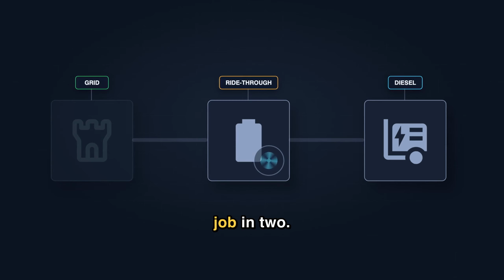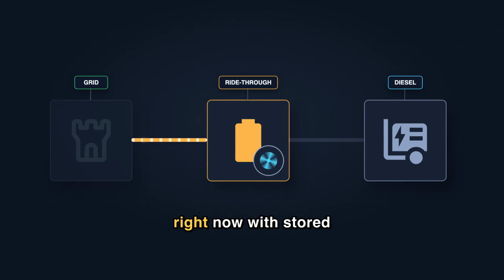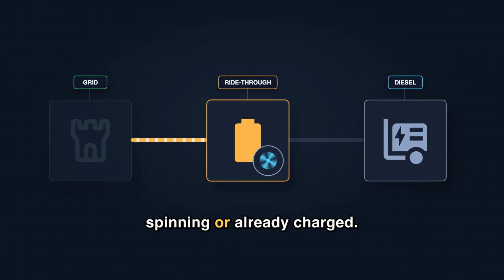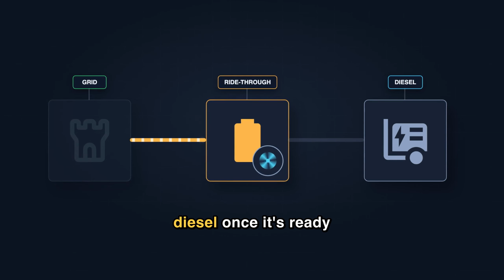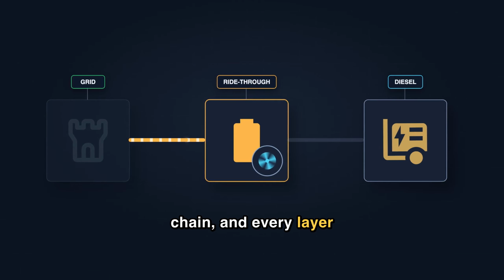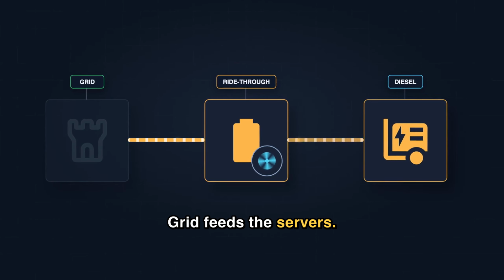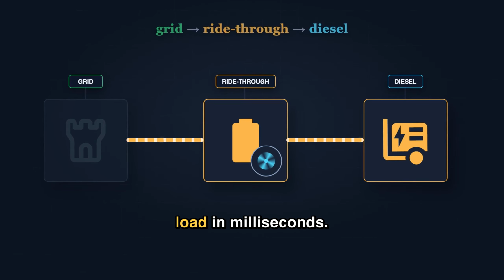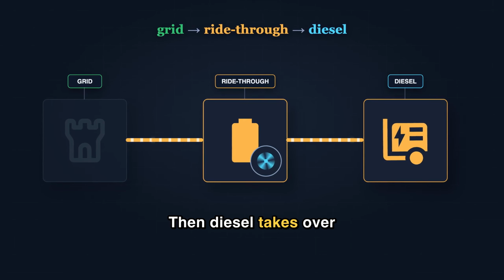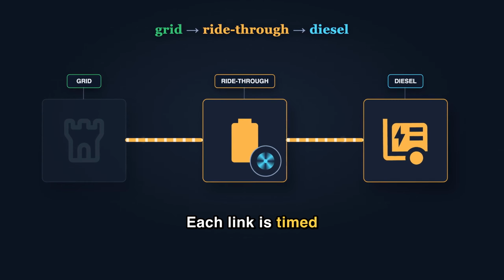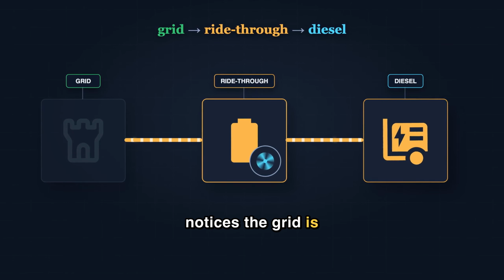So engineers split the job in two. First, bridge the gap right now with stored energy that's already spinning or already charged. Second, hand off to diesel once it's ready to carry the weight for hours. That gives us a chain, and every layer has one job. Grid feeds the servers. When the grid dies, a battery or a flywheel, the ride-through, catches the load in milliseconds. Then diesel takes over for the long haul. Each link is timed so the load never notices the grid is gone.